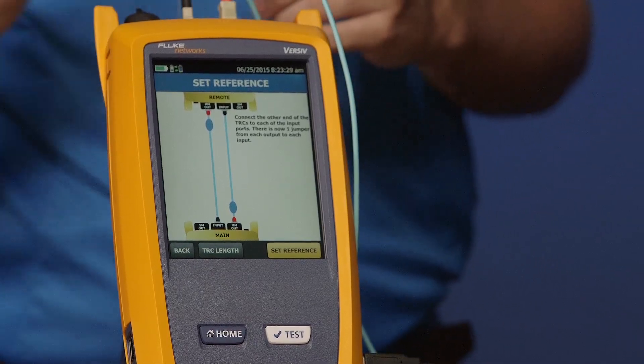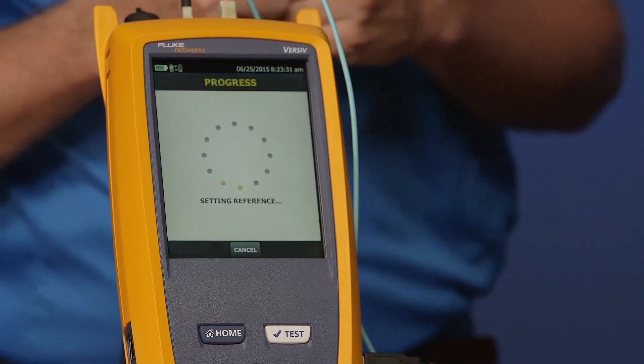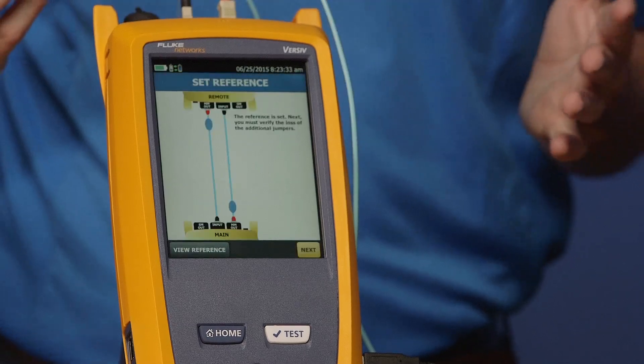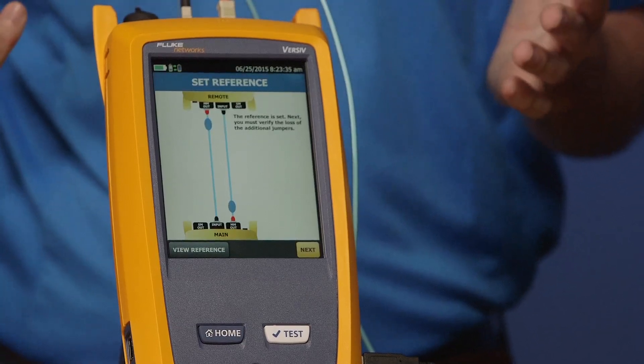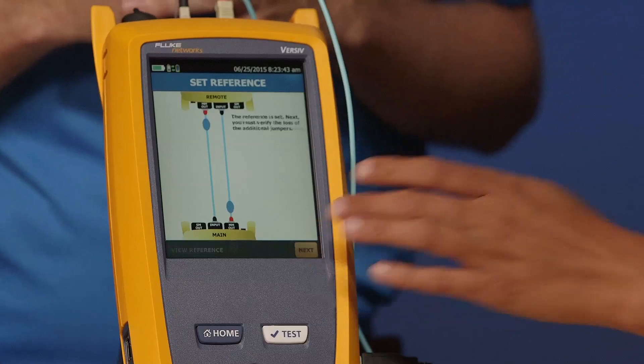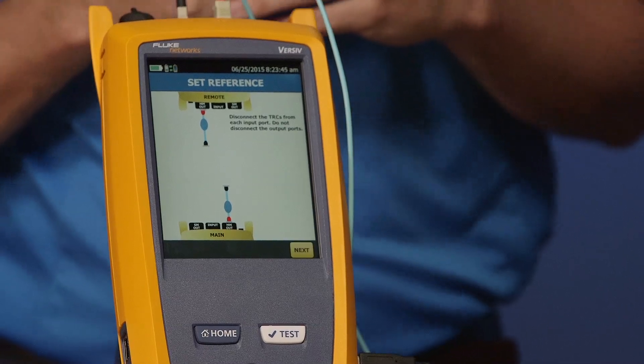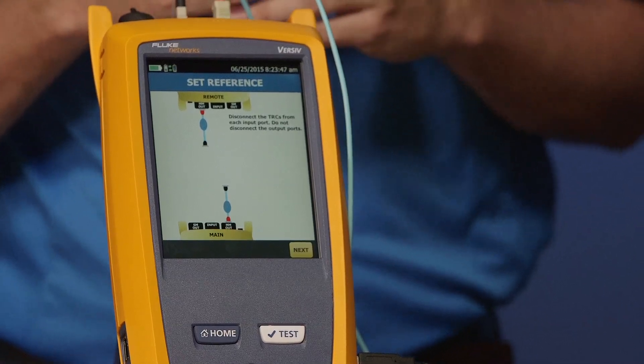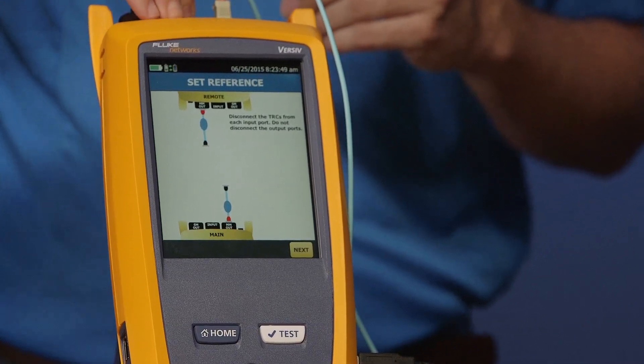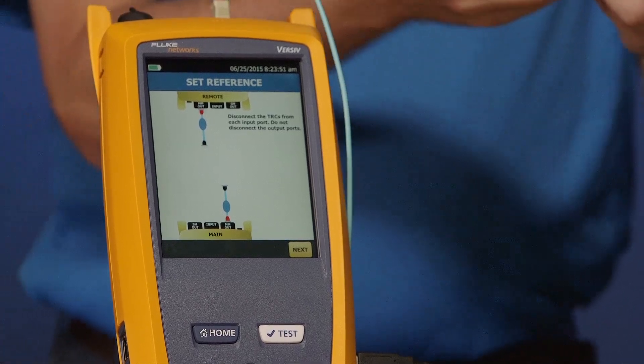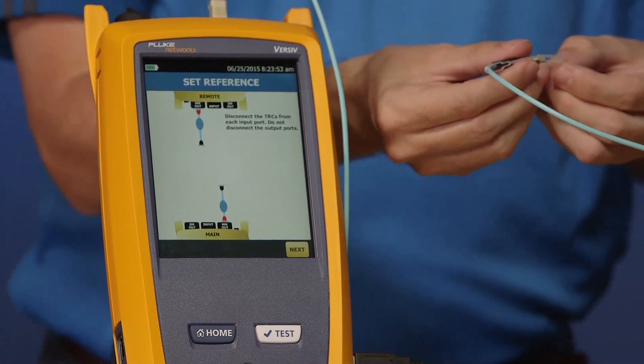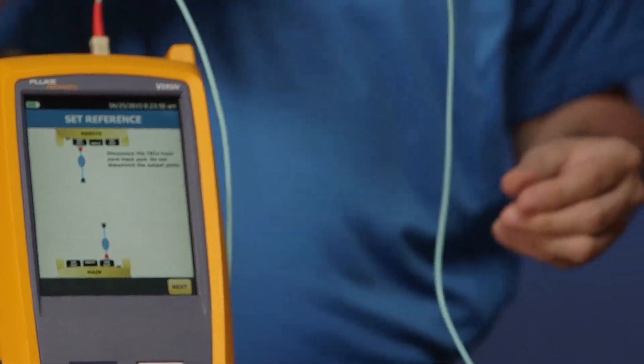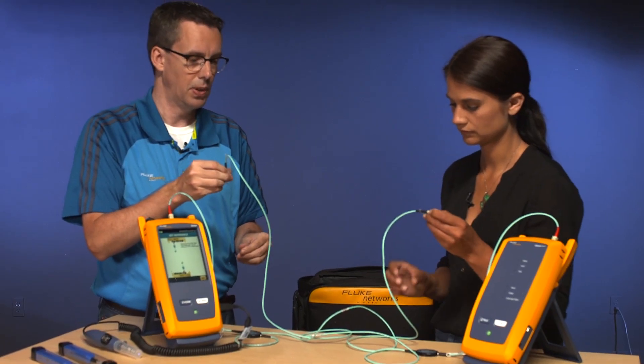Go ahead and tap Set Reference. This takes about three seconds — a lot quicker than the DTX which took about 12 seconds. Our reference is set; we've zeroed out these cords. Go ahead and tap Next. It wants us to disconnect from the input ports — we'll do that. We never ever disconnect from the output ports; the moment you disconnect from the output port that invalidates the reference.